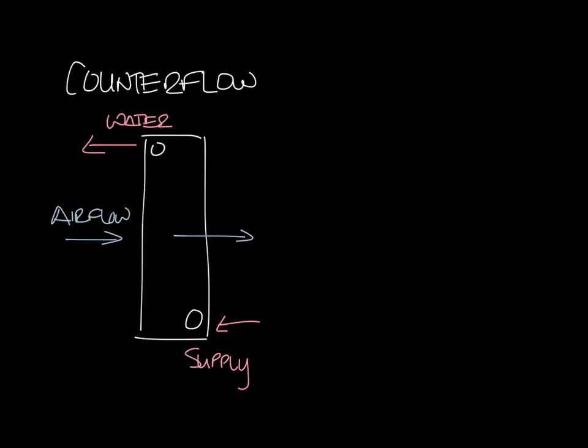So if this was a hot water coil on a VAV box, the cold supply air coming in would see the coldest water temperature first, and then as the air moved through the coil, it would move towards the warmer temperature water.